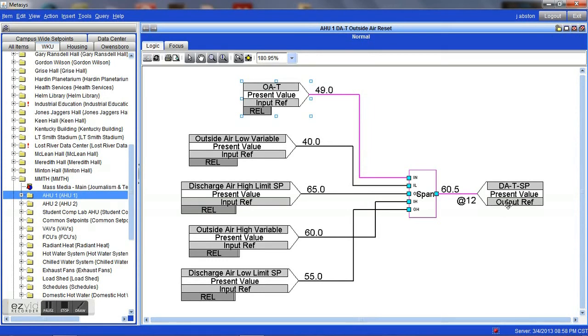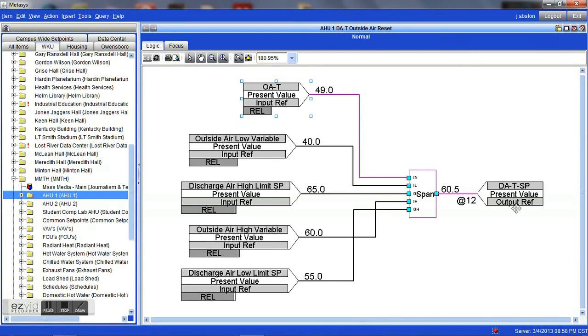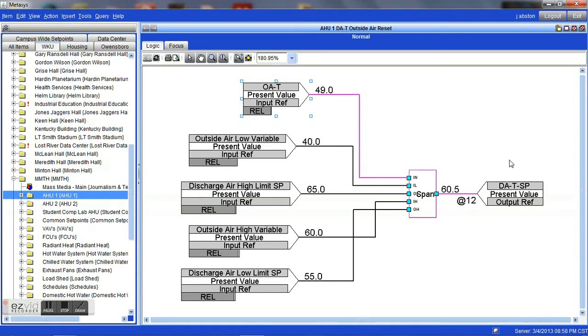By increasing the discharge air temperature slightly, you unload the hot water reheat or the electric or whatever type of reheat system you have, using the main air handler to heat the space, allowing less demand from those reheat systems, while at the same time having a cool enough temperature to cool any spaces that go above set point. A perfect example, computer labs that sort of thing that have a large heat load.